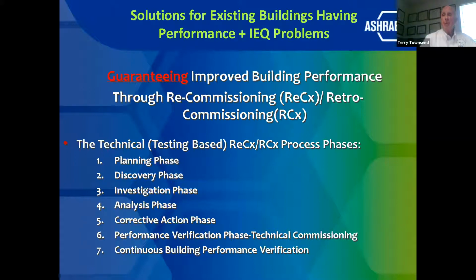If you're doing your job properly as a commissioning authority, most building owners, as well as maintenance staff, do not have time to monitor as they should. If you do a good job for them, what I've always said, you would have a job for life in this continuous building performance verification and monitoring, if they look to you. Now, one of the things that I do in my commissioning process is when we do retrocommissioning or recommissioning, we take the building representatives around with us and we show them what we find, and then we show them how it is corrected. Again, many of them do not have the time or the capability to do these corrections. And so if you do it correctly and do it properly, you've got a customer for life.